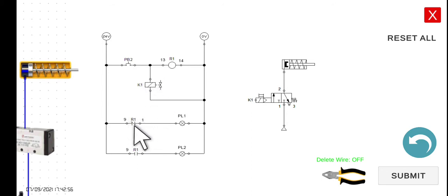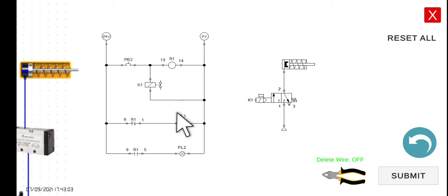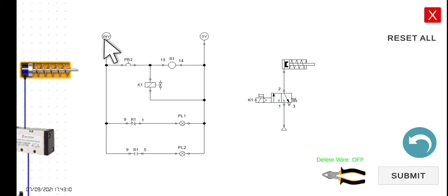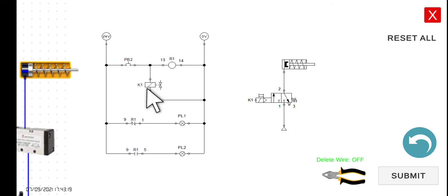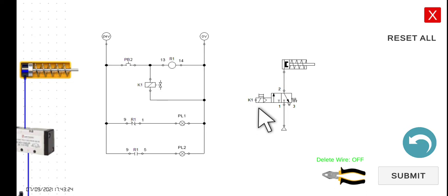This is the normally closed contact of R1 and the normally open connection of R1. So what we're trying to do here: if we press PB2, current will now be able to flow to R1. Since K1 is connected in parallel with R1, the moment we press it, K1 will also activate, and this portion here will be activated. So if this one activates, the solenoid will move.